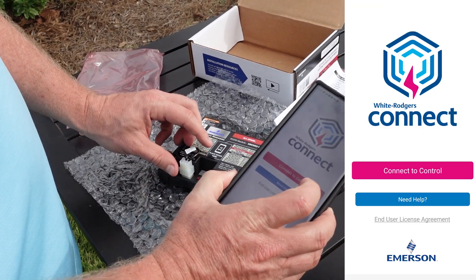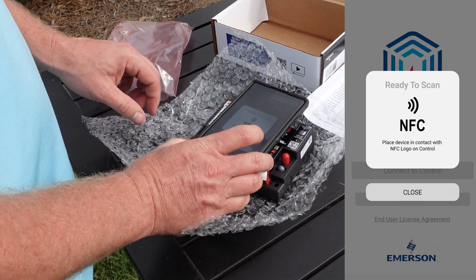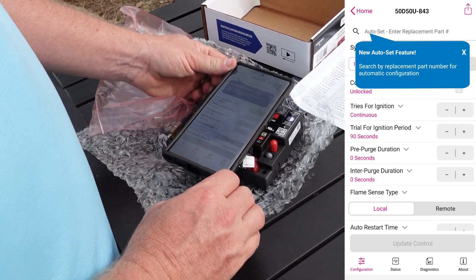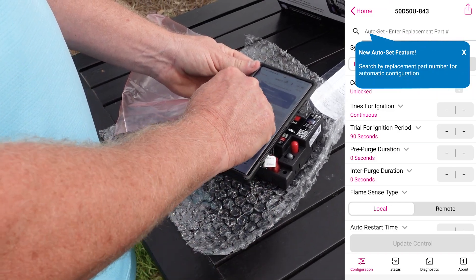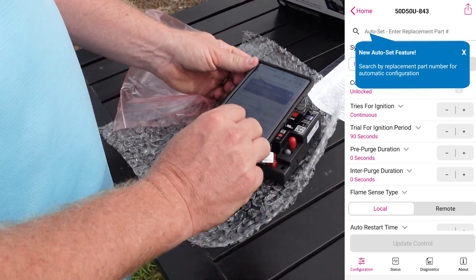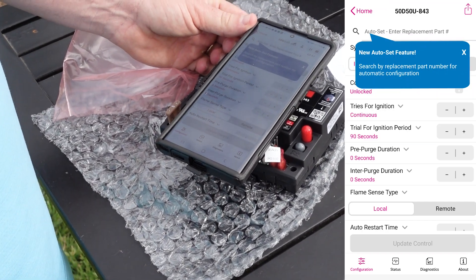Now we're going to connect the mobile device. The White-Rodgers Connect app comes with Near Field Communication, or NFC, technology, which links the AllSpark directly to your mobile device. The AllSpark doesn't need to be powered on, and no Wi-Fi, cell service, or password is required. Now that the device recognizes the AllSpark, we can put in the part number that we're replacing, and it will automatically configure everything in the system based on that number.